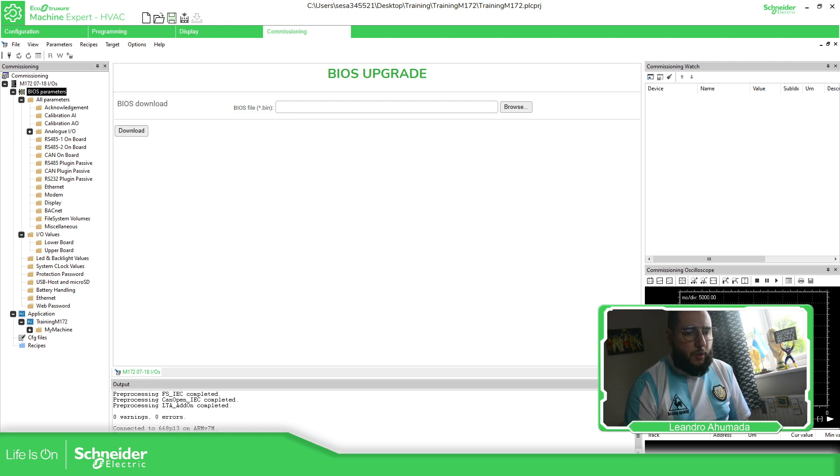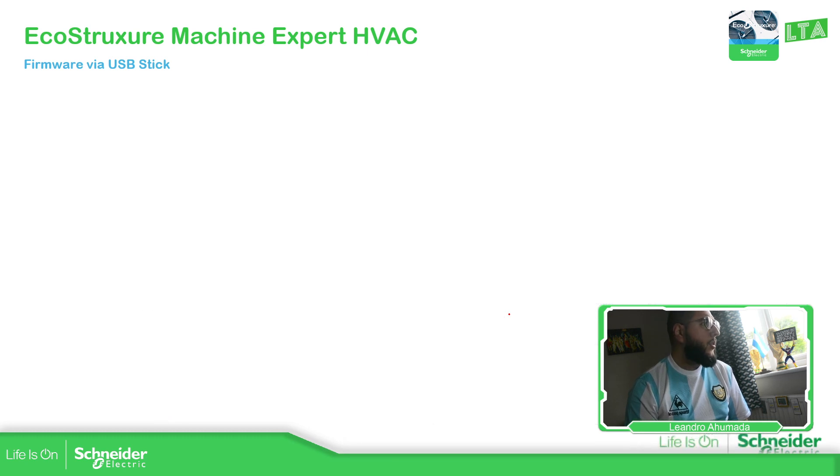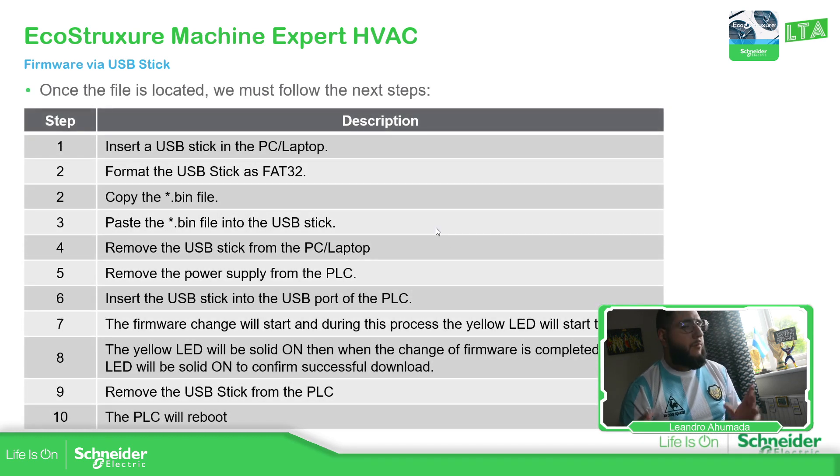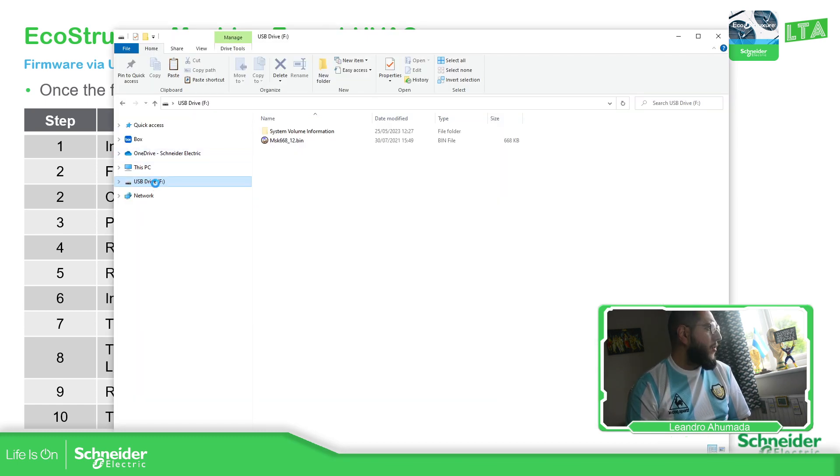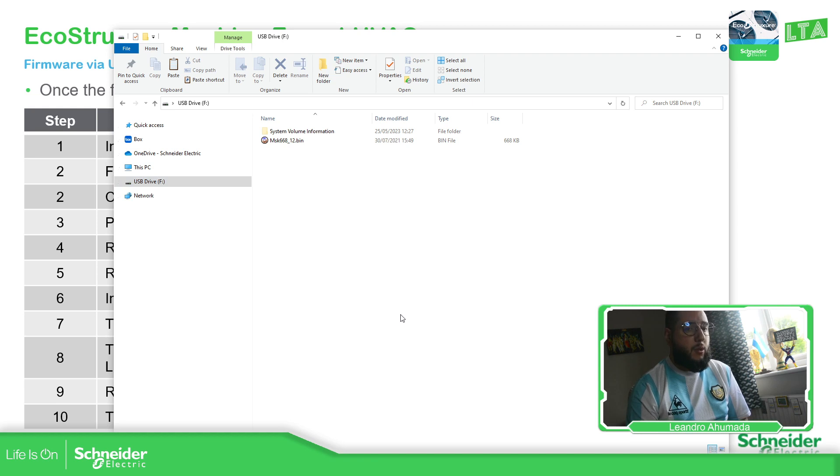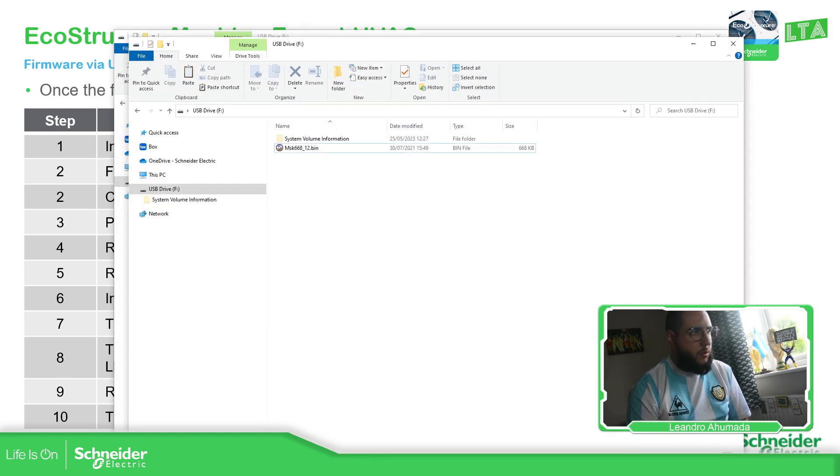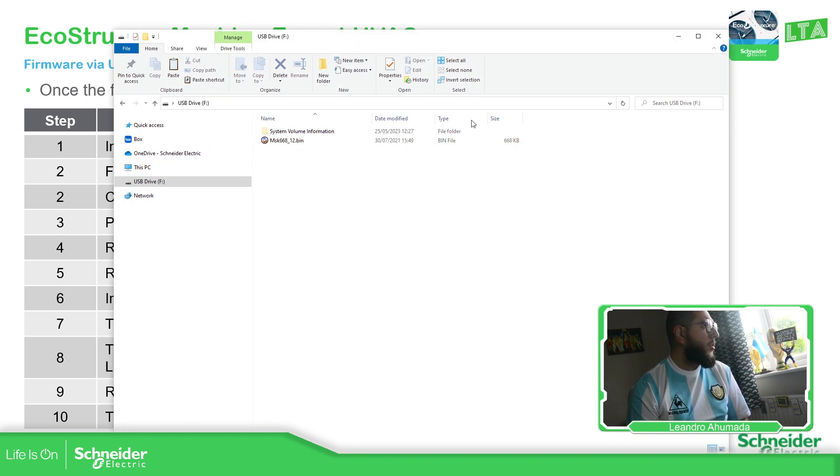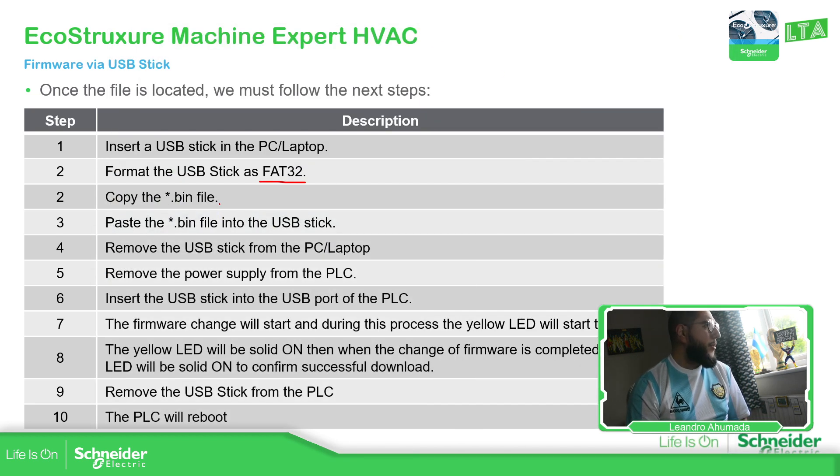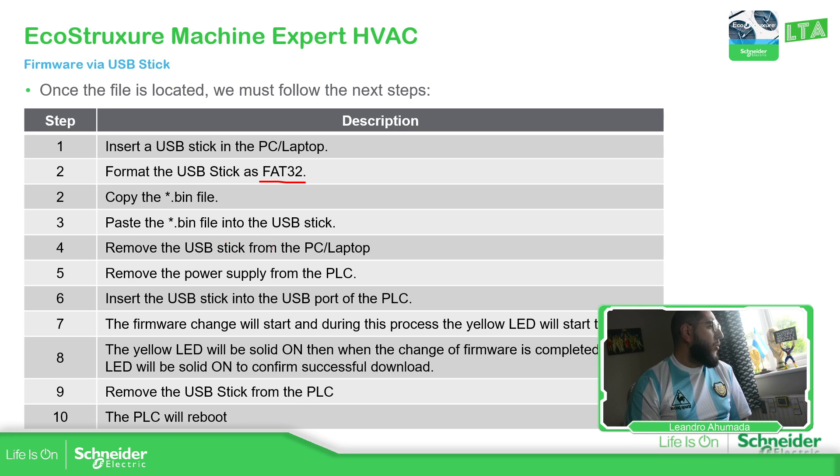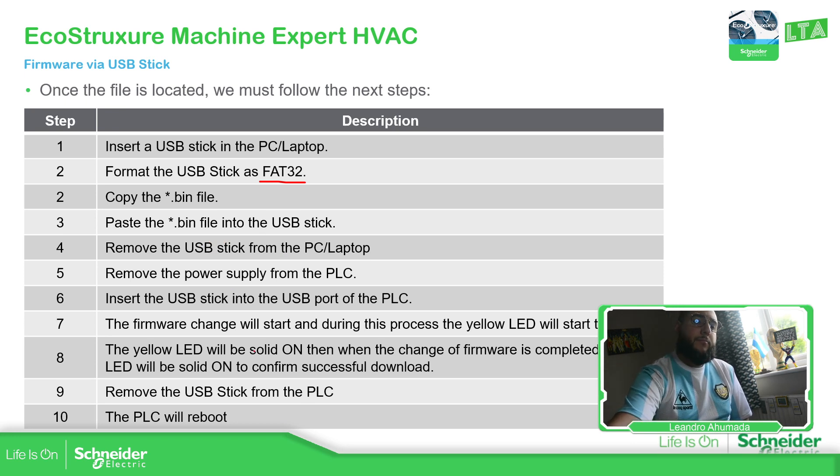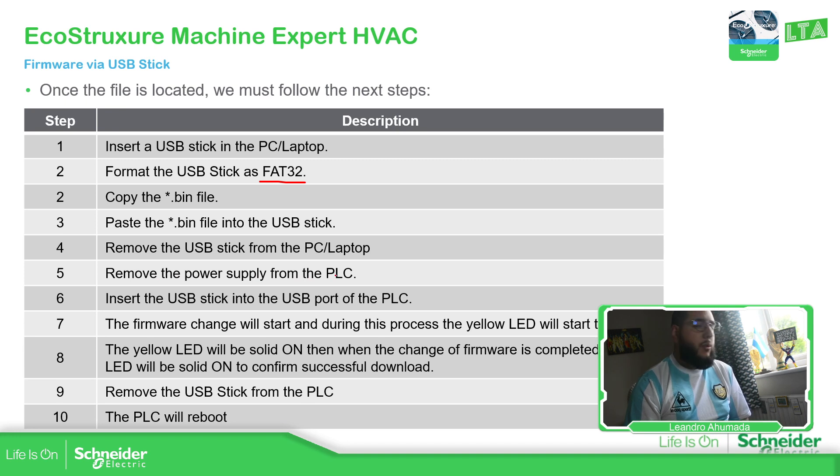So if we go back to the presentation, we copy and paste the firmware that we want. Then this is the procedure. Format the USB in FAT32 format and everything is going to be deleted. If we format it, it's going to be formatted in the format that you require. Now copy the bin file and put it on the USB. We have already done this part. Now we just remove the USB from the laptop.